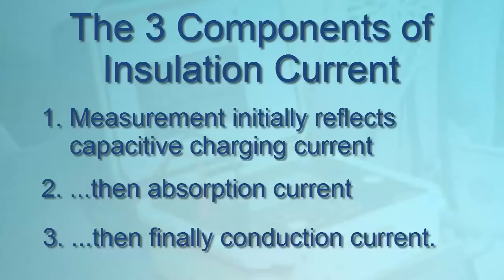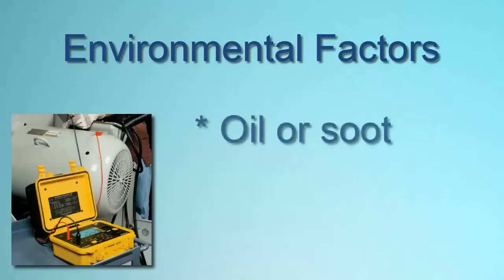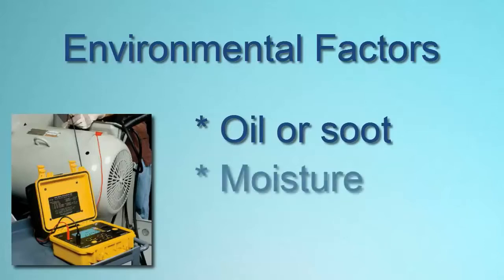Understanding how these individual currents contribute to the total insulation current can help you correctly interpret the results you receive when performing a test. It's also important to be mindful of how environmental factors can affect resistance. For example, oil or soot on the equipment surface can lower insulation resistance. If any equipment surface temperature is at or below the dew point of the ambient air, thermal moisture forms, which can significantly lower the equipment's resistive value.